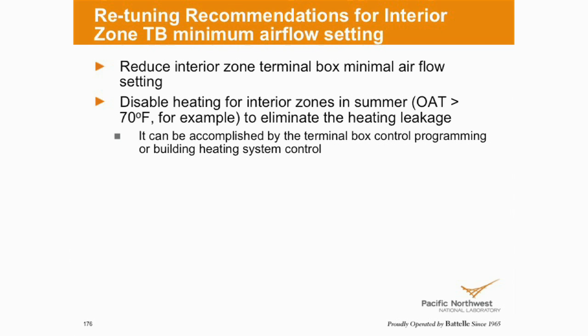So let me interrupt just for a second. What Gupong's saying here is that if you reduce your minimum CFM settings for your boxes, typical design parameters are generally excessive. And so by reducing it, you may be able to maintain your space temperatures with reduced airflow settings. This can be pretty significant, especially if you can shut off your reheat system.